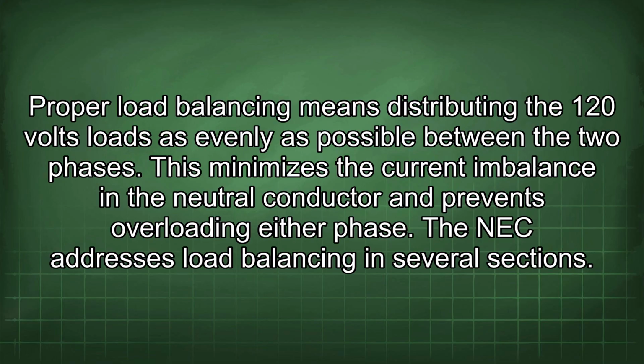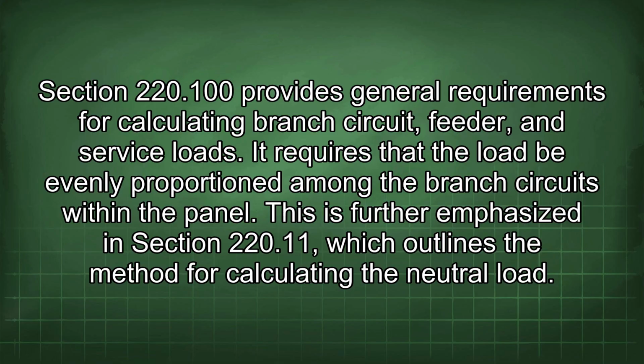The NEC addresses load balancing in several sections. Section 220.100 provides general requirements for calculating branch circuit, feeder, and service loads. It requires that the load be evenly proportioned among the branch circuits within the panel. This is further emphasized in Section 220.11, which outlines the method for calculating the neutral load.